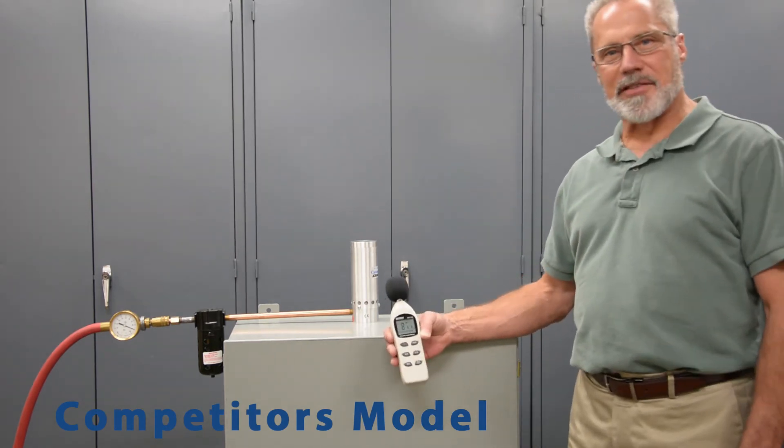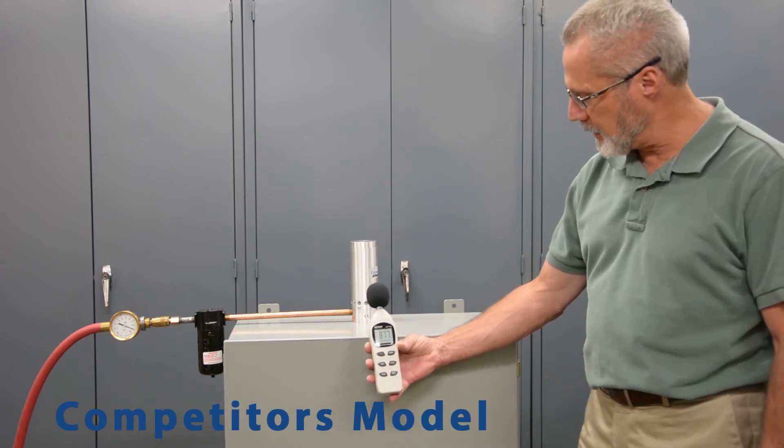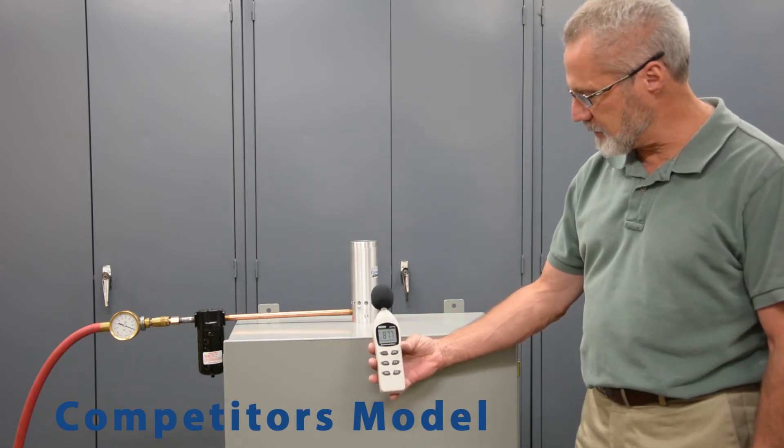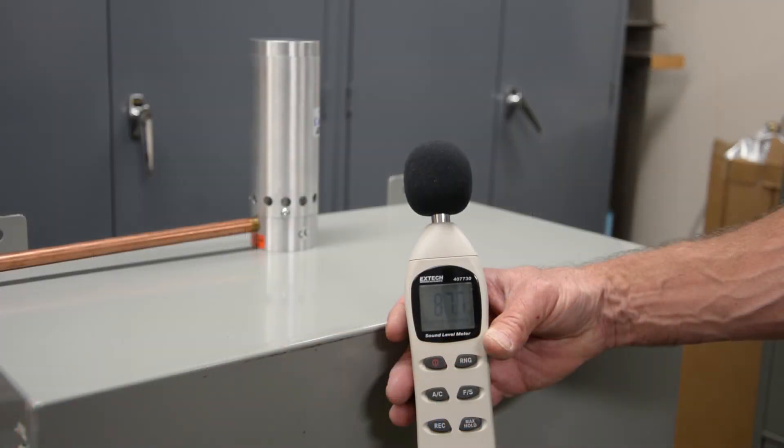I'm measuring the sound level at one foot away from the cooler. As you can see the sound level is between 87 and 88 DBA at one foot away.